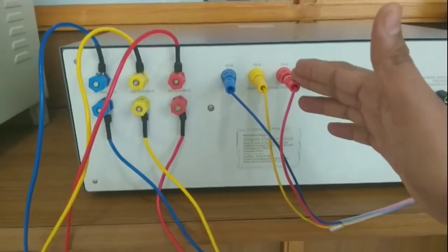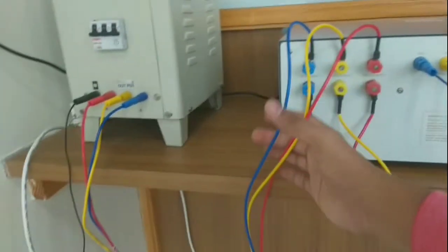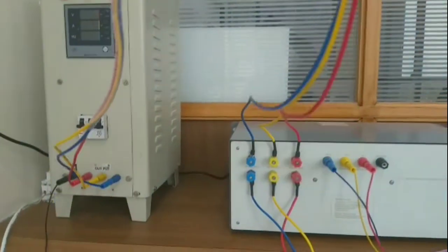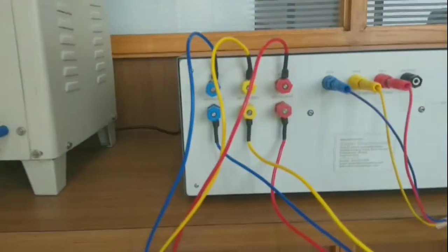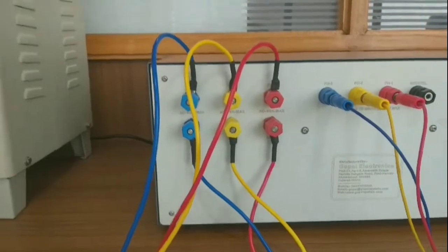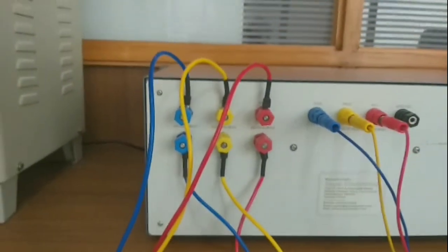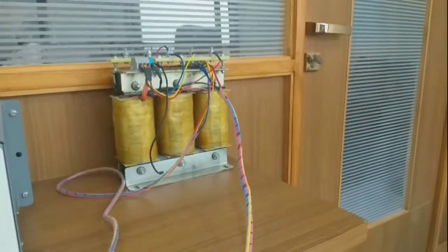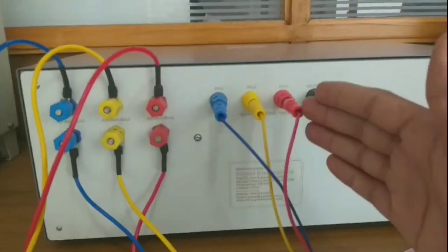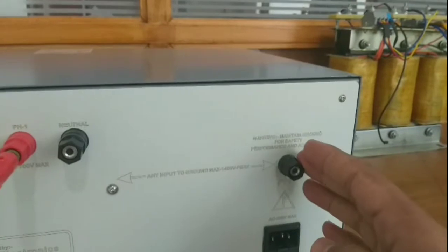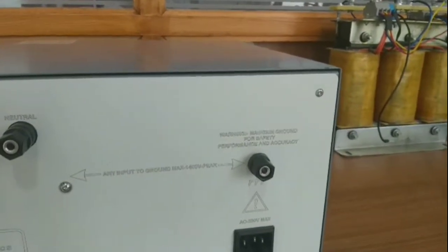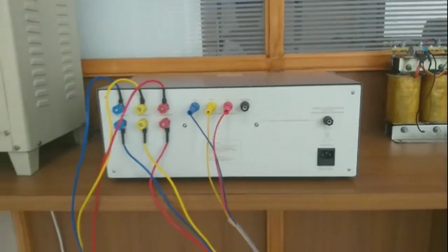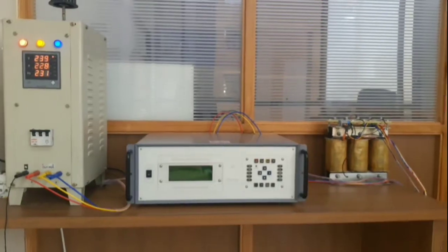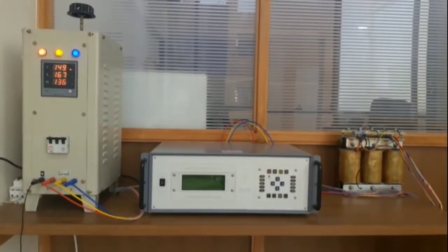This is the voltage measurement channel and this is the current measurement channel. The variac output is connected to the current measurement channel at the top side as a source, and the transformer primary is connected to the current measurement channel at the bottom side as a load. This is all done for current measurement. For voltage measurement, we need to measure voltage at the load terminal. For that, we have connected the voltage measurement channel to the transformer's primary. This is the neutral port and this is the earthing port, so you need to connect earthing properly. This is all done for connection. This is how our entire setup is.